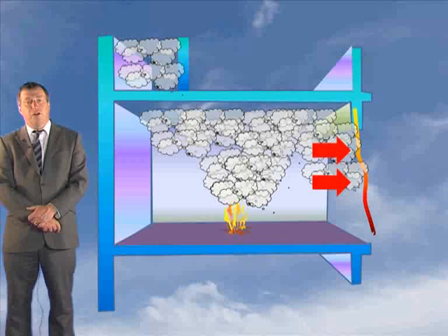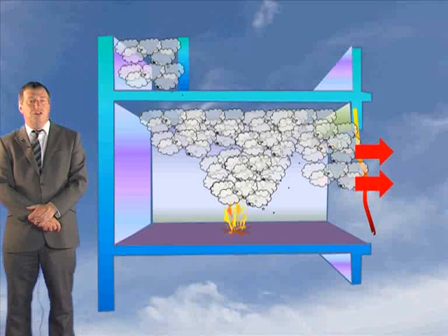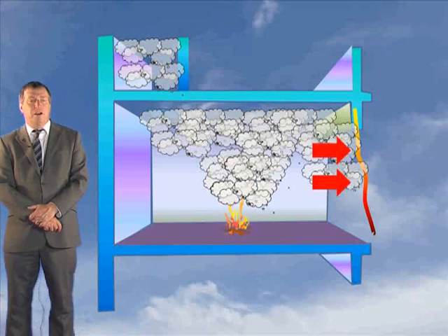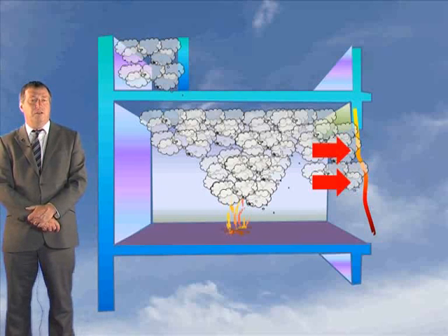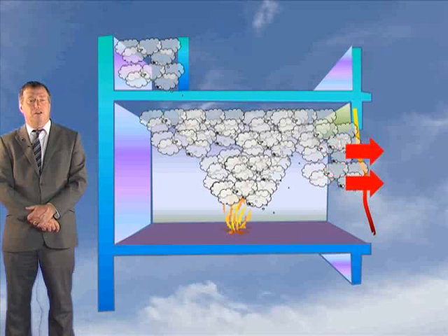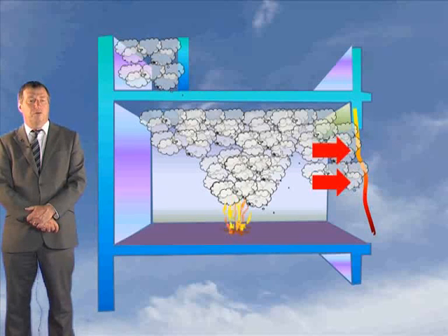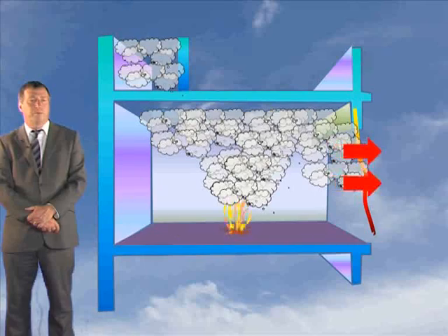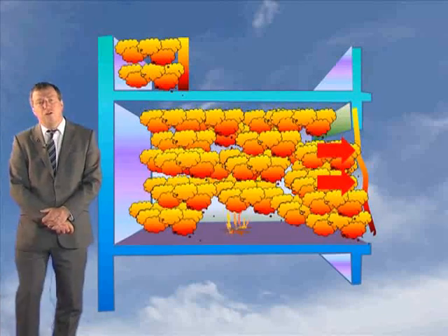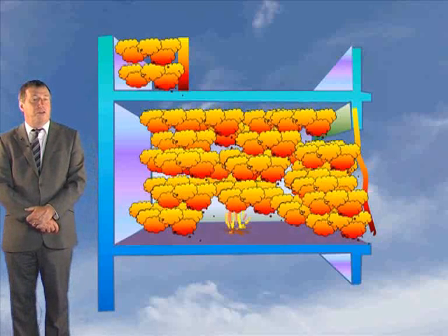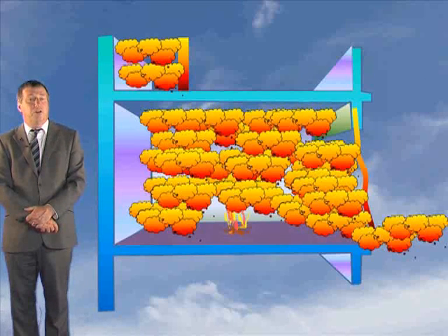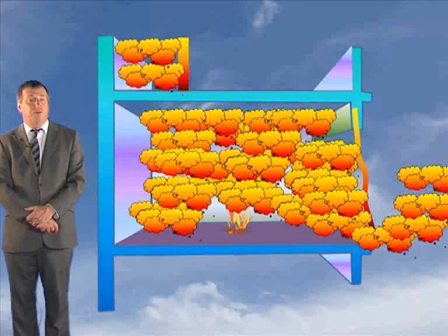The buoyancy of the hot smoke layer exerts a pressure on the surfaces containing the layer, and this pressure acts on the curtain as if it were a sail, pushing it sideways. This is something that needs to be considered where the curtains are not secured at the sides within guide rails. If the pressure is too great, then the sideways deflection becomes significant, and the bottom edge of the curtain lifts, and the vertical depth of the curtain may not be sufficient to contain the smoke layer, causing the SHEVS to fail to achieve its design purpose.